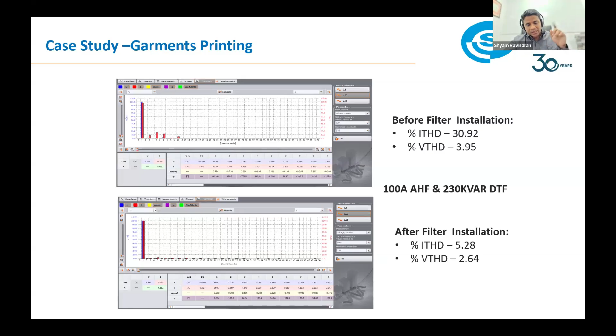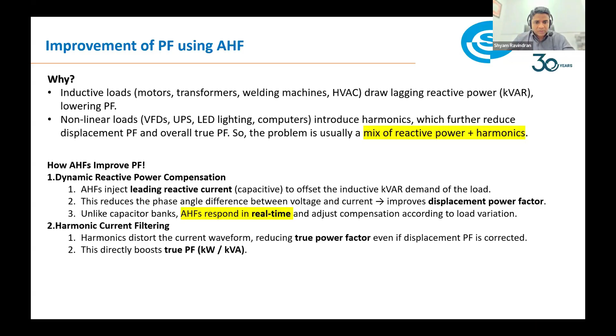Now, in the beginning, I mentioned power factor. An improvement in power factor actually improves electricity savings. It is true, because when you do power factor improvement through an active harmonic filter, the right word, as I highlighted, is real time. The compensation adjusts to the load variation much more quickly than our old systems, so the power factor improvement happens much quicker and we are able to maintain the power factor. And in kVAh billing, not kWh but kVAh billing, we could actually identify the electricity savings as well.